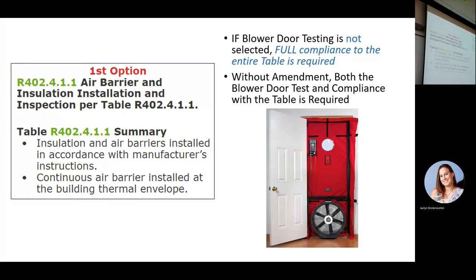But we pressurize or depressurize the house with the fan running, and we adjust the fan speed until it's just kind of sitting there at that steady pressure in the house. You see the two tubes? Maybe if you're close you can. There's a tube that's measuring outside pressure and the inside pressure.